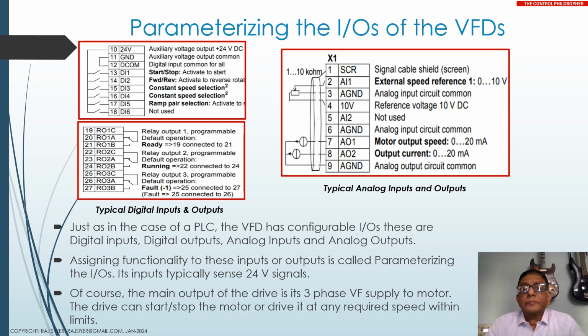In the same way, you can use the analog outputs to represent something. These analog outputs can be wired as analog inputs to a PLC system. Analog inputs can be had from a pressure transmitter or a level transmitter, and the drive can be configured to respond to these signals. Drives also have built-in PID functions, which will maintain the pressure if these analog inputs are used for measuring the pressure. Got it?